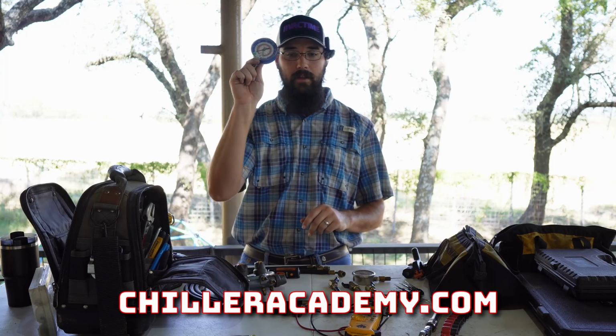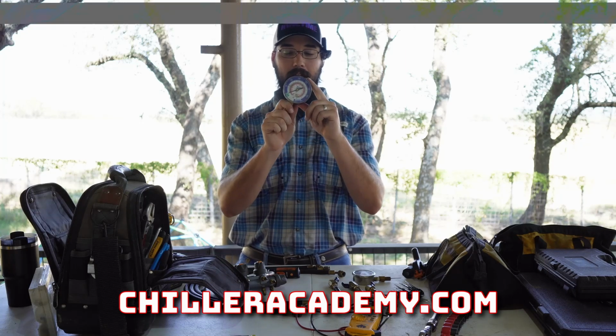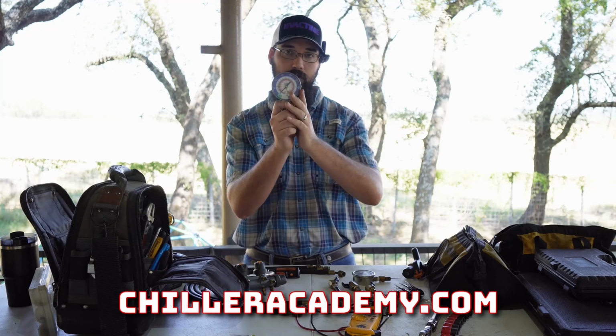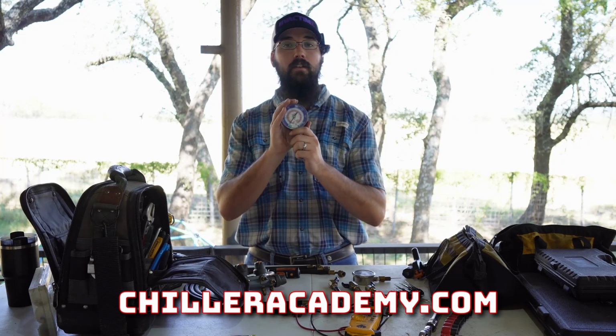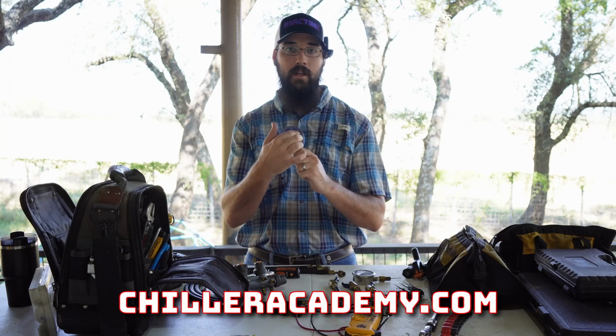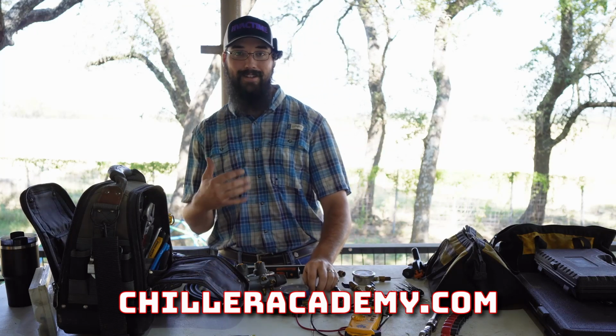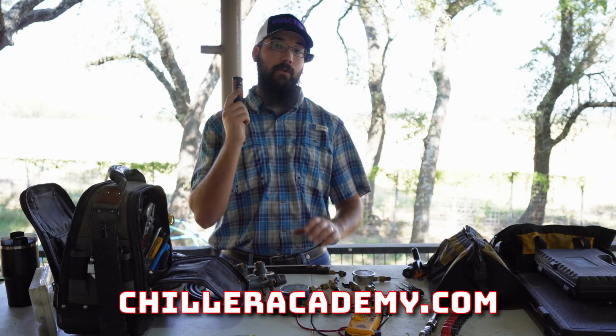That is where I do recommend having a set of analog gauges. Have a set of these on hand, a low side gauge and a high side gauge, so that when you are doing calibration, you have something that is real time. As pressure is building, these needles are swinging and moving. There's no delay or lag here. It is instantaneous.